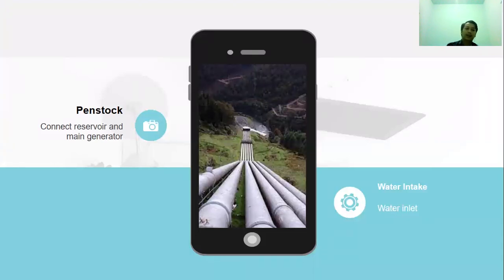Here we have a picture of penstock. Before water goes inside the penstock, it comes from the water inlet. Penstock are open or closed ducts which carry water to the turbine. They are generally made of reinforced concrete or steel. Concrete penstock are suitable for low heads, lower than 30 meters, as greater pressure causes rapid deterioration of concrete. For 30 meters or higher, steel penstock is needed. The steel penstock can be designed for any head. The thickness of the penstock will be increased with the head or the working pressure.